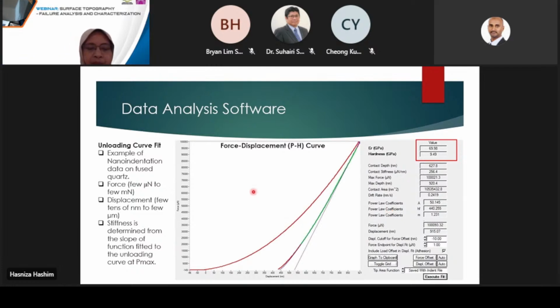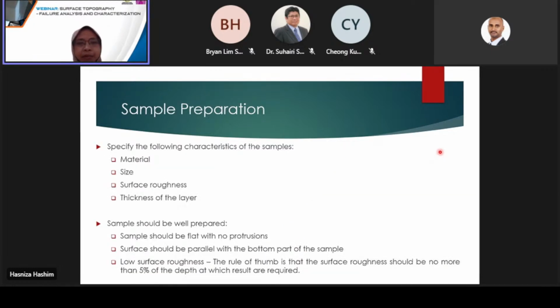In this slide, I show you what the data analysis software looks like after you have loaded a force displacement curve from the nano indentation experiment. Now we have this force displacement curve. What we can do is click on the execute fit button, and then the software will automatically pull a stored tip area, then calculate the maximum force. It also detects the unloading curve and measures the slope, and then calculates the projected contact area. And then, of course, with all this information being pulled, it gives you the values of hardness and modulus here at the top. Well, that wraps up all the background theory that I have for this presentation.